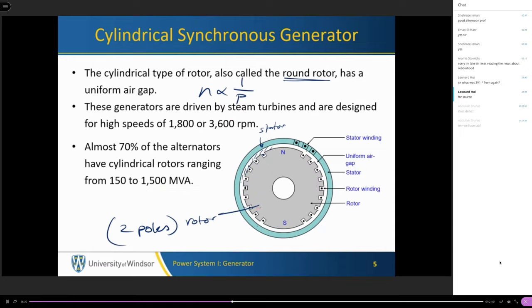And that is why this type of machine is used with steam turbines. Steam turbines run at high speeds, like 1800 or 3600 RPM. So round rotors are typically used with steam turbines or thermal power plants, and that is why this is very common in power generation, like nuclear, coal-fired, gas-based, and steam-based power plants. They use round or cylindrical synchronous generators.